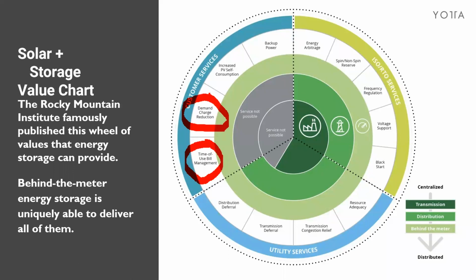Demand charge reduction is really nice because we are able to use CTs to monitor the consumption of the building that this is on. The CT is basically a controller. The controller talks to the gateway, which then talks to the batteries on the roof. Let's say you have a surge during the day, a big demand.